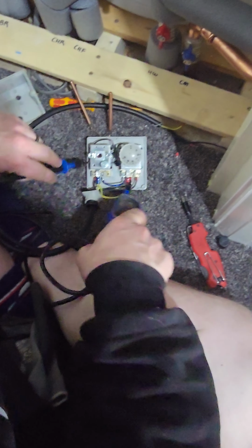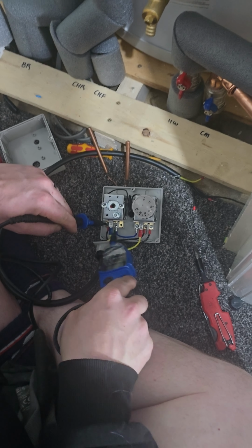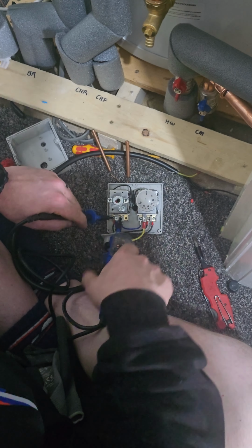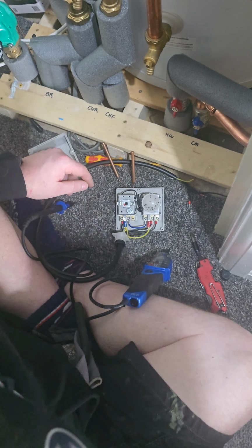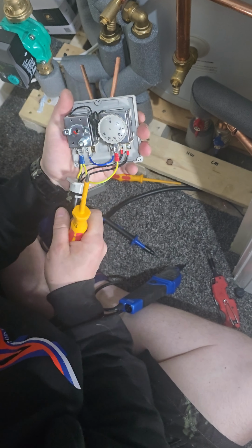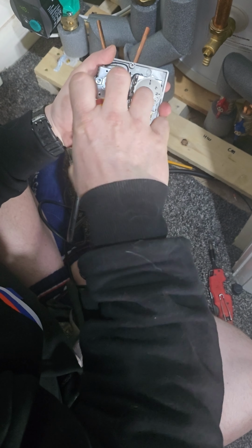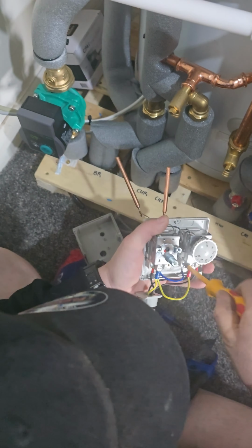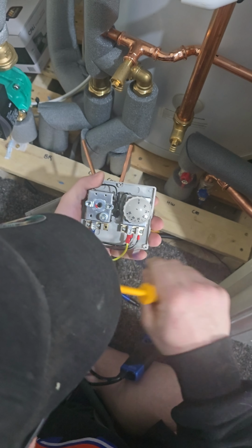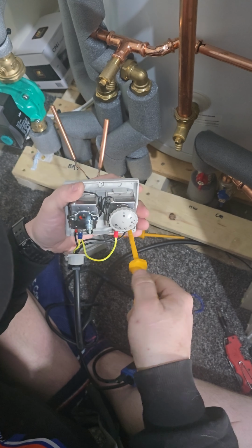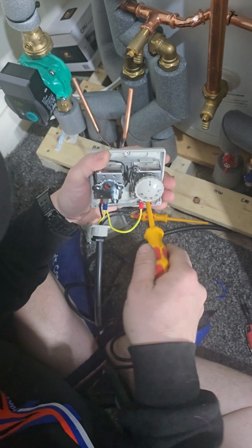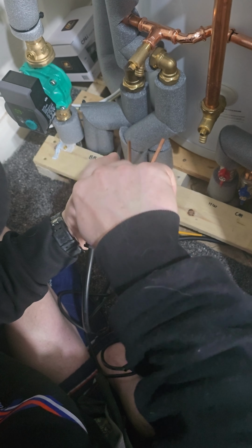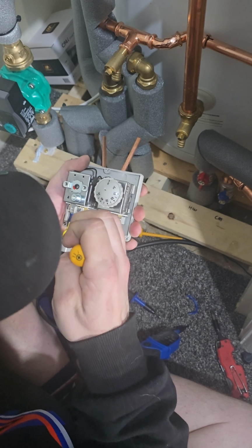Now, we don't need the thermostat, we want the high limit stat. So what we're going to do is, we've got this contact here to this contact here because it's not overheated. So we're going to remove with the screwdriver, pause it, and we're back. So we're going to remove this link here, get rid of that there, and then we're going to get rid of this one here because we don't want anything coming live by accident. And we're going to take this one here, or either of those, it really doesn't matter, just pick one basically. I'm going to pick one here and take it off if it lets me.